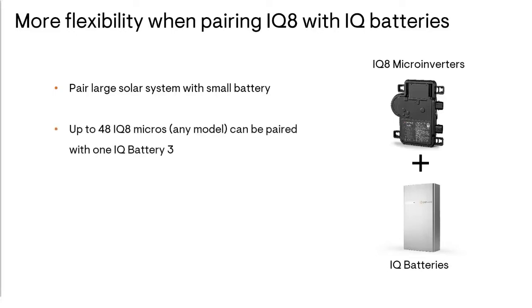If you are installing just one IQ battery 3, there is another limit to be aware of, which is quite high relative to the previous, and that is a maximum of 48 IQ8 series microinverters. It doesn't matter which model, it could be the IQ8 or 8 Plus or any of the others, but a maximum of 48 can be installed with just a single IQ battery 3.